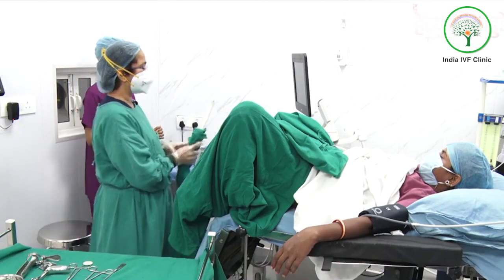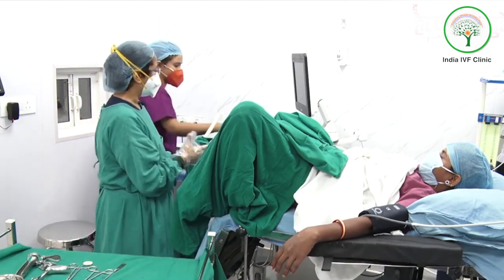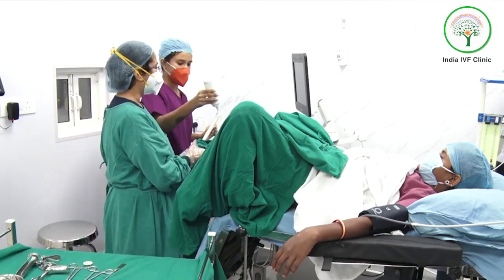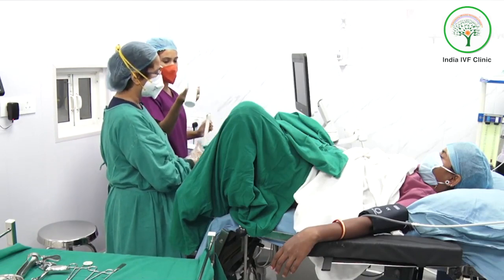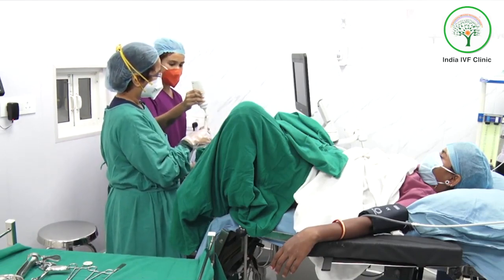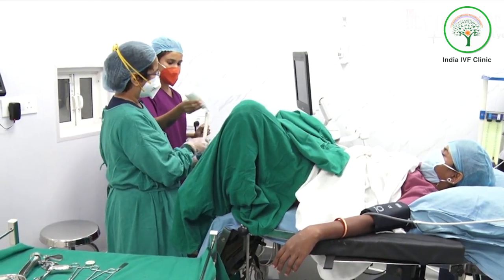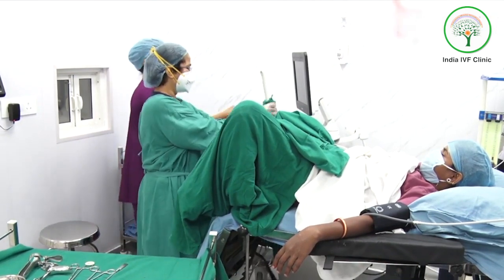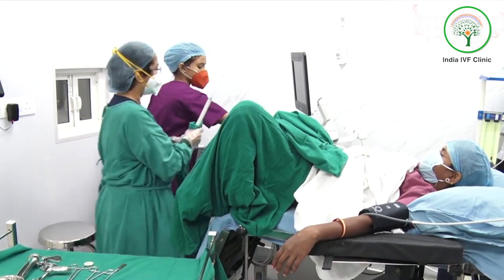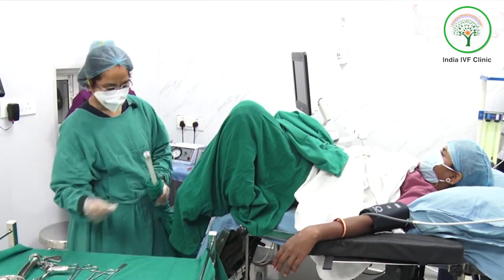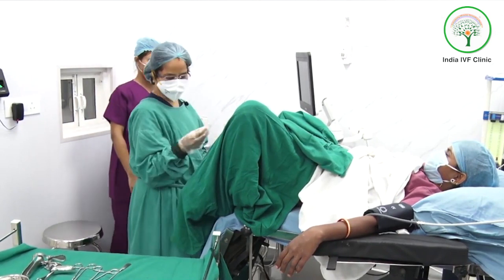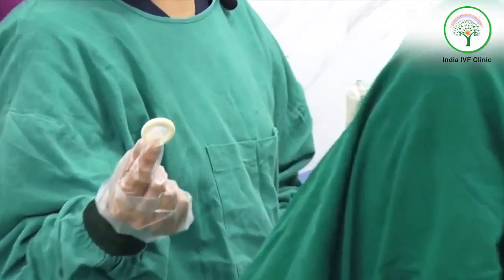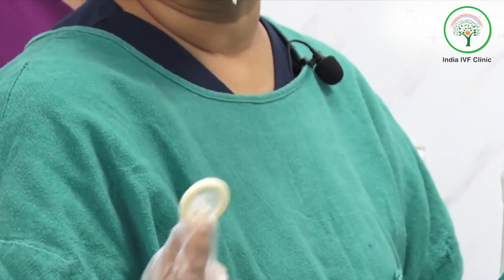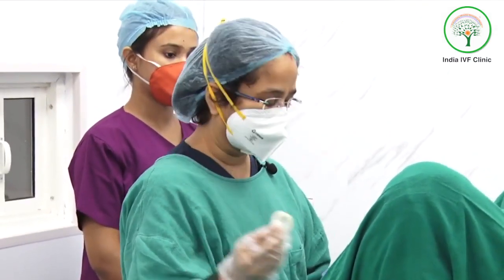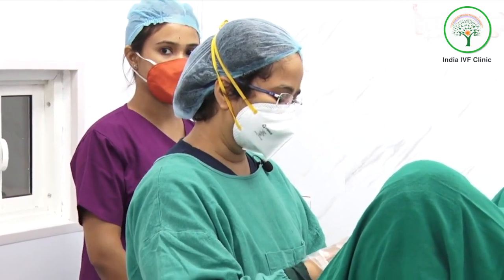Now the jelly has to be applied on the probe. You have to make sure you are not touching the jelly with the same hands. It is very essential that you apply the jelly on the inside of the probe, because there has to be no contact, no touch. This probe cover is also not the usual condom that you use. It should not have any jelly, because these are all gametotoxic, so you cannot use it. So now the probe is covered with it.